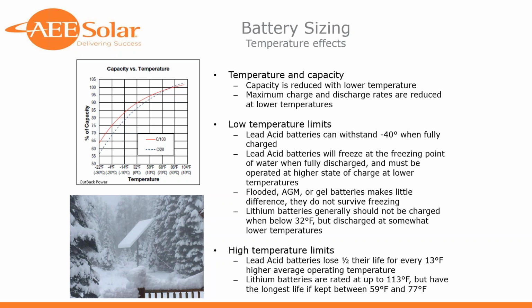So generally, you've got just an issue with capacity. When they're colder, your capacity is not going to be as great. Your discharge current is not going to be as great. And then there's also hard limits on temperature. If you discharge a lead battery and then take it below freezing, it will freeze inside. The water part of it will freeze inside, which damages the battery, regardless of what any marketing hype tells you. I have seen it virtually always destroys the battery if you freeze it. Some say that it will withstand that, but maybe only in a laboratory.